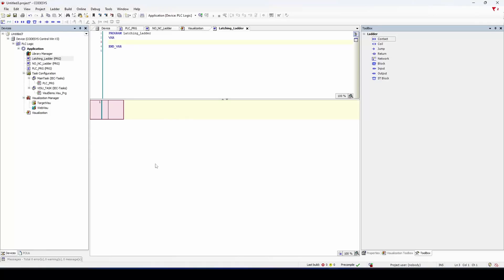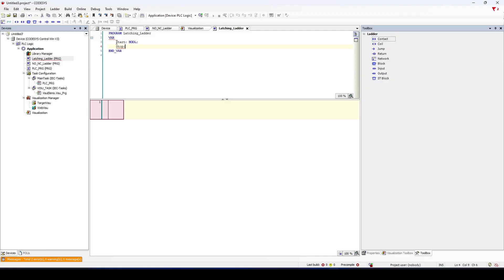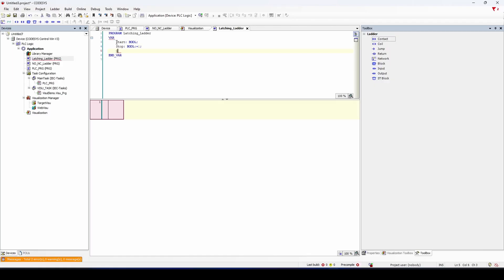All right, let's build a start-stop latching circuit here in ladder logic. So we're going to start with a start bool, a stop bool, which we're going to set equal to one on initial startup here, because a stop button is usually a normally closed contact on the back of the button. And then we're going to do an output, which is also a bool. So this could be a lamp, it could be a motor, it could be any of those types of outputs.